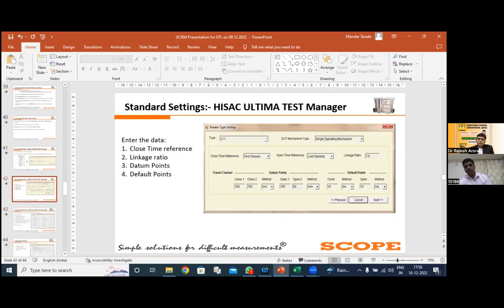Moving ahead, here you will get the references: first the close time reference, then the open time reference. Whenever we perform the close operation, many bounces come into the picture. Some people are willing to see the bounces, some are not. So if you change the reference to first closure or last closure, you get the reflection in your timing. Then, according to the linkage ratio we feed in here, you get the contact travel, because contact travel is equal to mechanism travel multiplied by the linkage ratio.